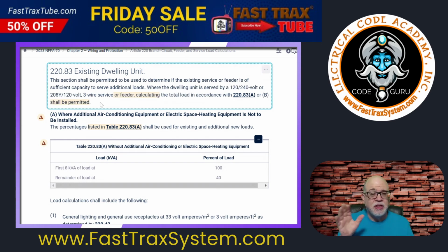Okay, so before I even look at this, a lot of myths that are out there say that you have to use this. You're permitted to do this, but you know what you could do? You could actually recalculate the load again as if you're starting from scratch: take all of the appliances, take all the variables that you would have in normally sizing a service, add in your new loads, and do it as if everything is new. That can determine the size of the service, and you compare it to what you already have. So this is permissive, but a lot of times it might be just as easy to do the whole calculation again. Every situation is going to be different.